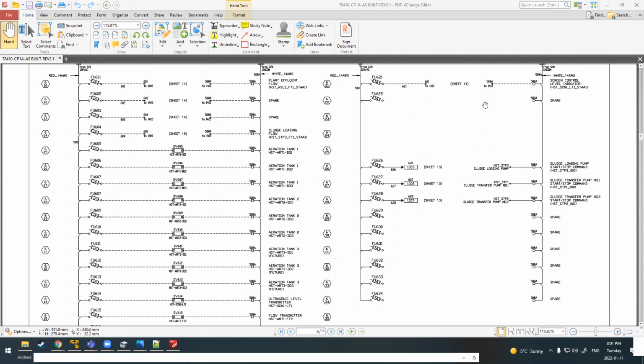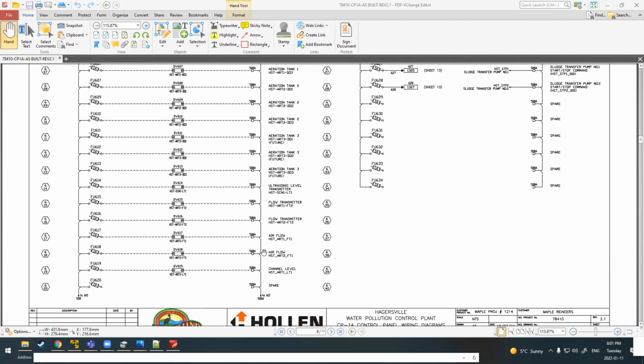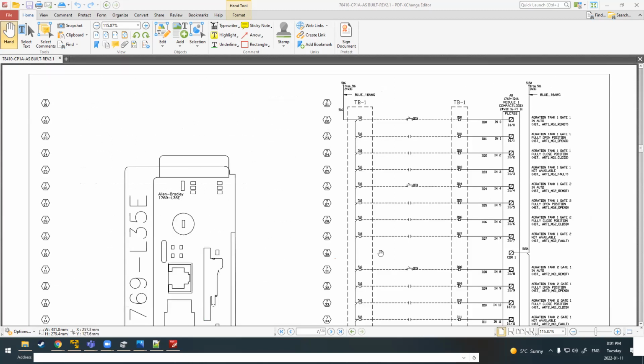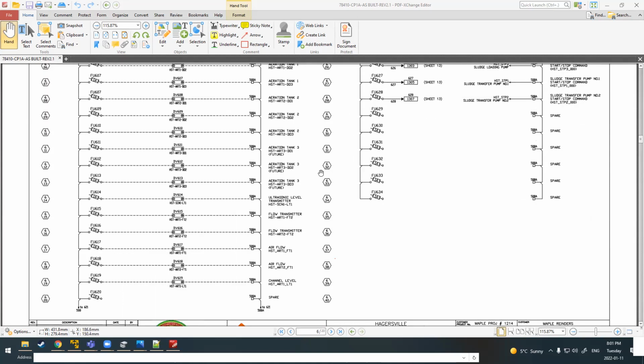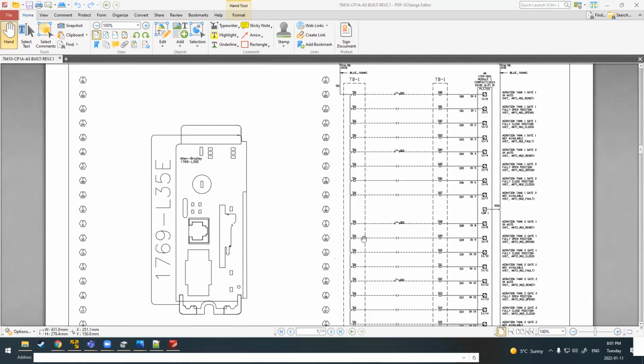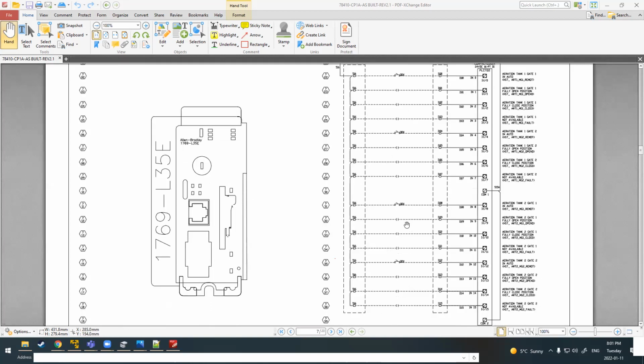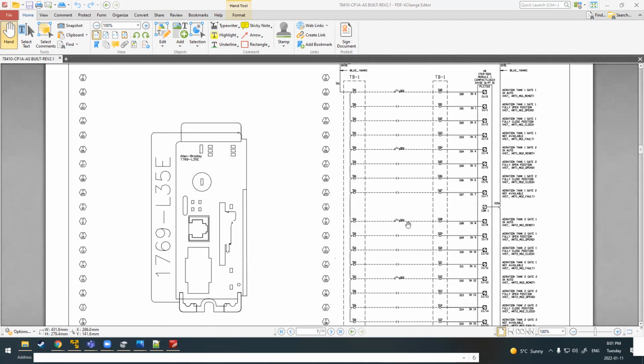Skimming down again, the rest of these are 120 volt devices. They just have power or they don't, based on the fuse. This is where we get into IO. So this drawing here shows we've got a 1769 L35E. That's an Allen Bradley Compact Logix processor. This is a Compact Logix processor input module.